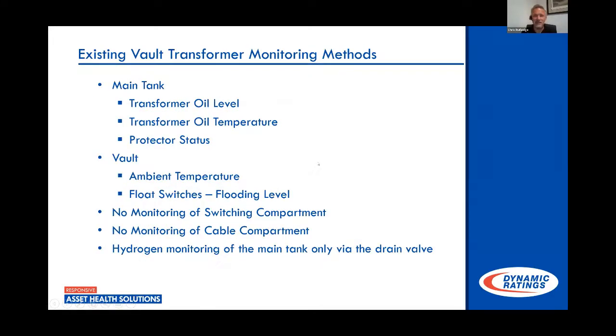So existing, kind of what I was seeing out there, people were looking at oil levels, oil temperatures, and the status of their protector. Most companies are bringing that into their SCADA to know if the protector is open or closed. And then there's a lot of monitoring involved. Some of these vaults can get pretty hot depending on what's going through them, so ambient temperature, and float switches are definitely a must-have for detecting flooding level in the vaults.